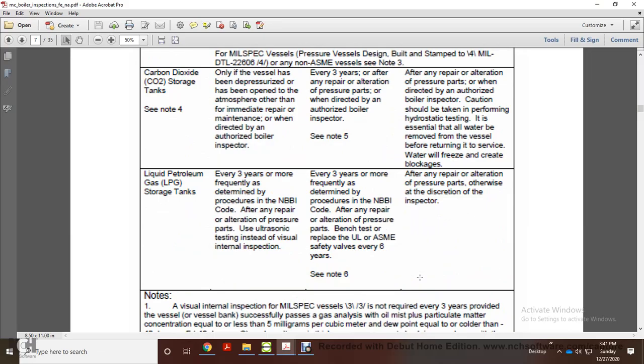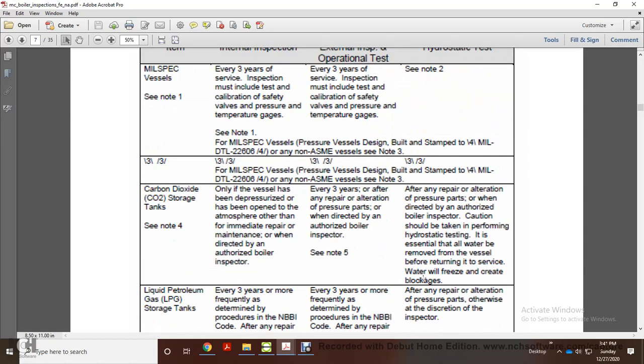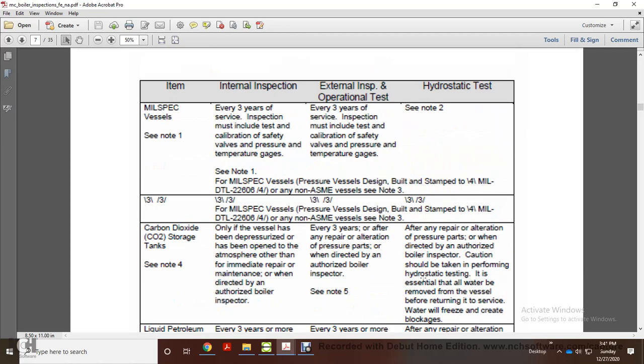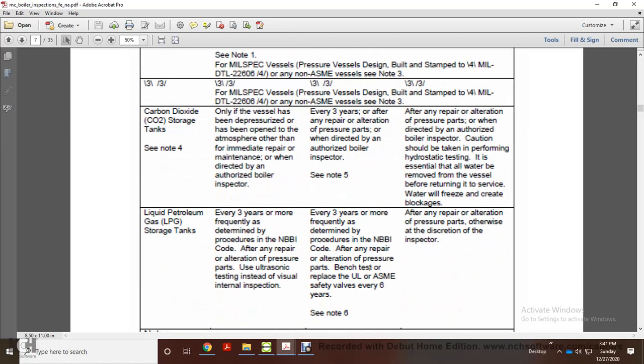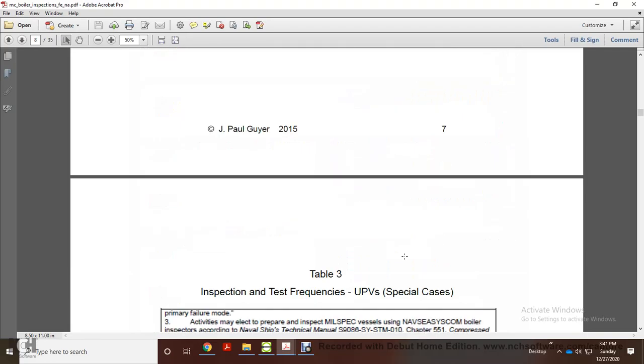After repairing alteration pressure parts, use ultrasonic testing instead of visual internal inspection. External inspection operational tests every 3 years determined with the procedure of the NBBI Code for the repair alteration pressure parts. Bench testing replaced with the UL ASME safety valves every 6 years. Hydrostatic testing after any repair alteration pressure parts, otherwise discretion by the inspector.